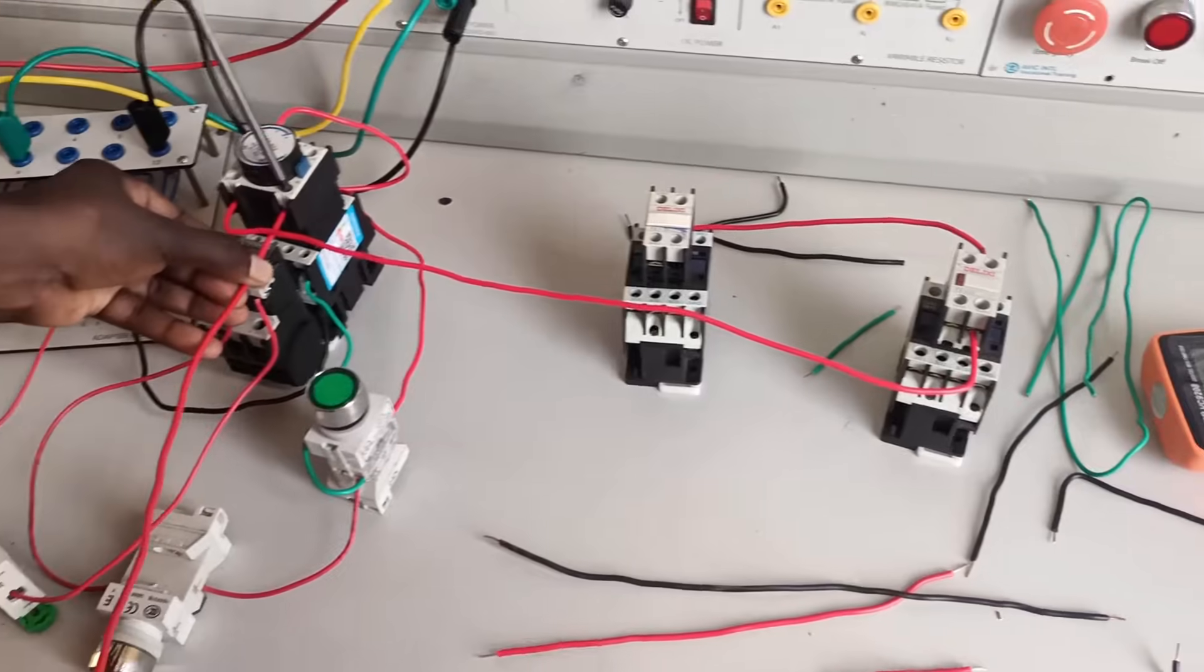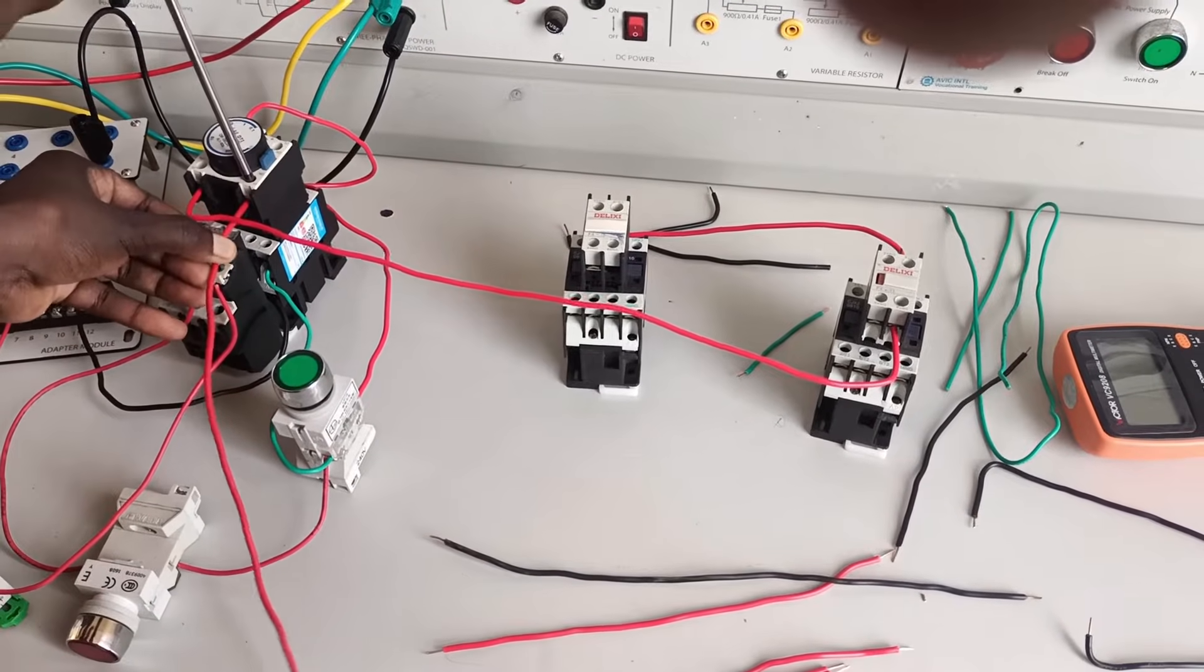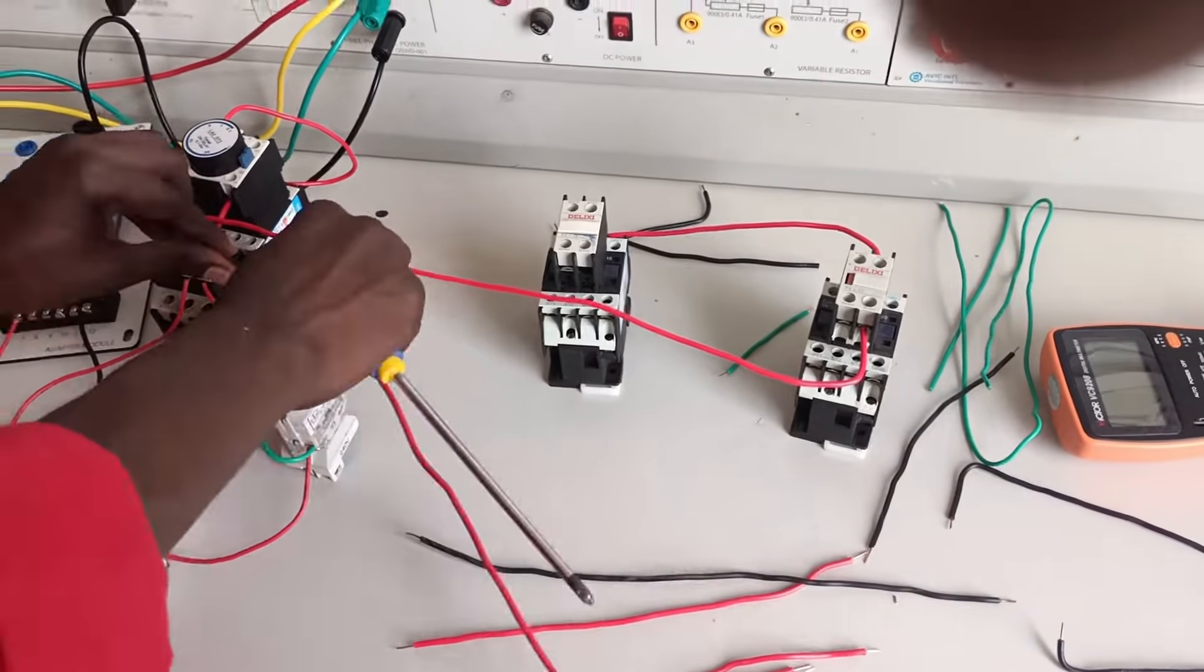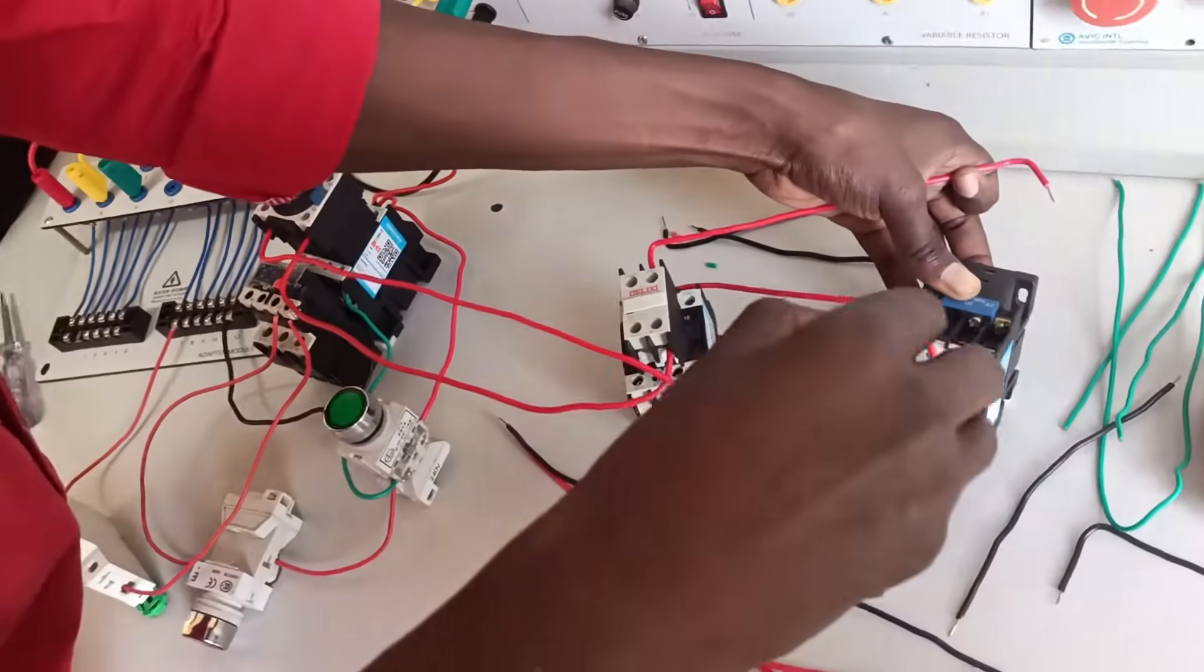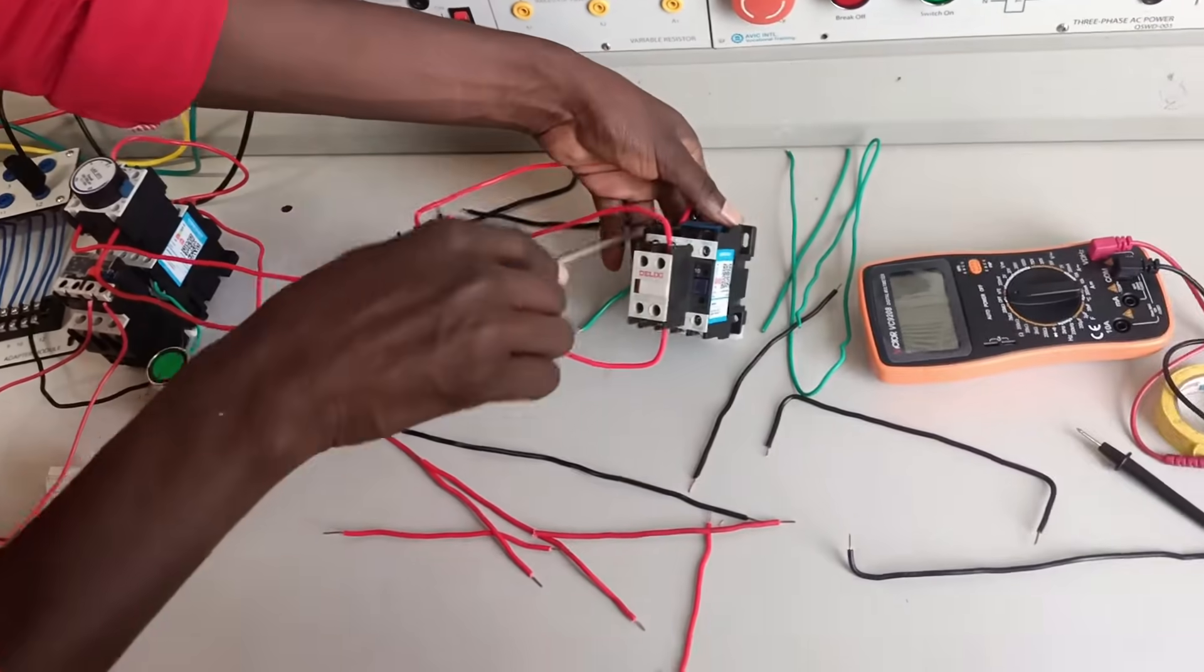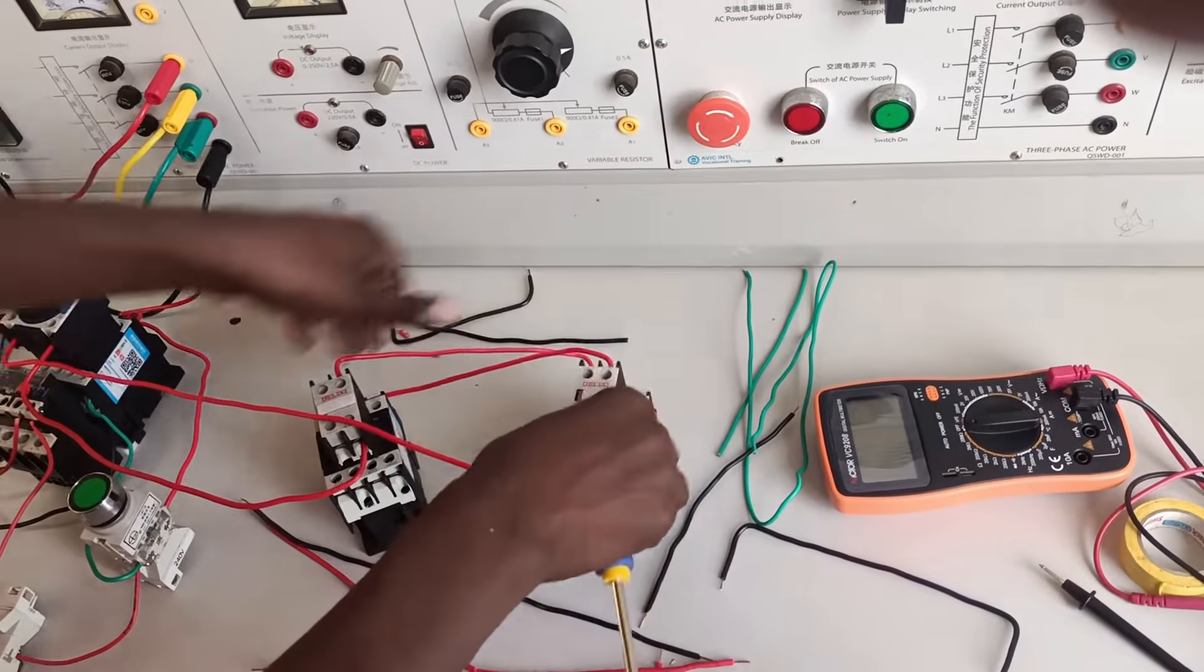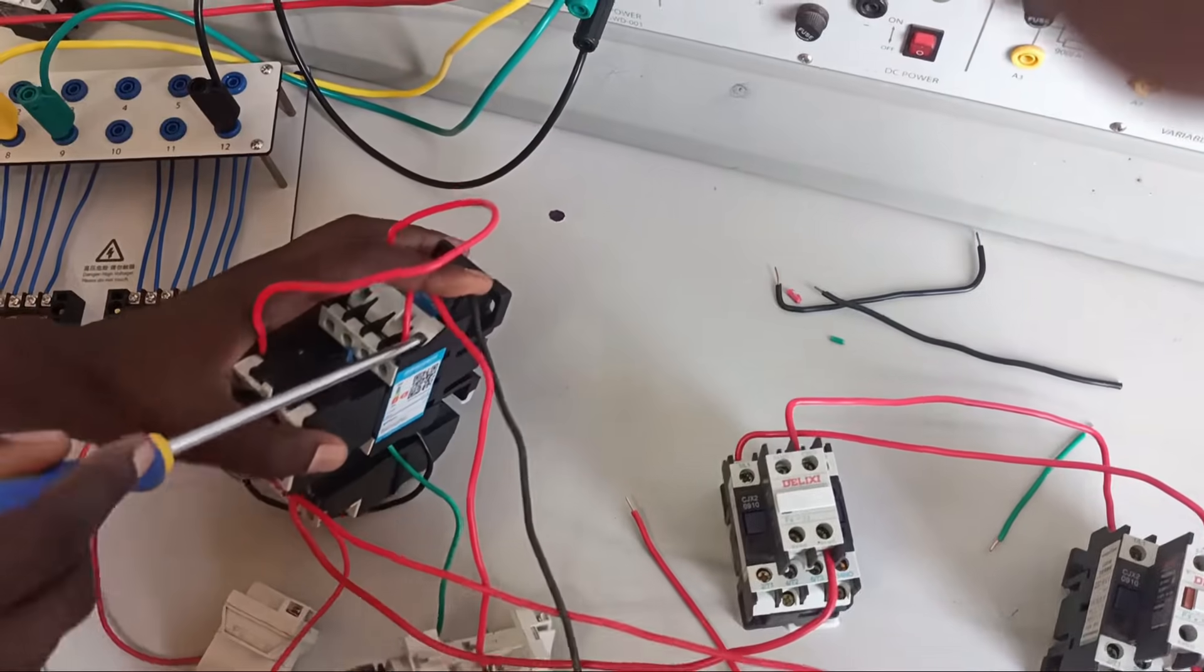And then the other one, from the normally open contact of the timer will go to the star A1, but through delta contactor, that is contactor 2. That's why you're seeing the normally closed terminals of the delta contactor, going to the A1 energizing coil of contactor 3. That one we call interlocking connection.